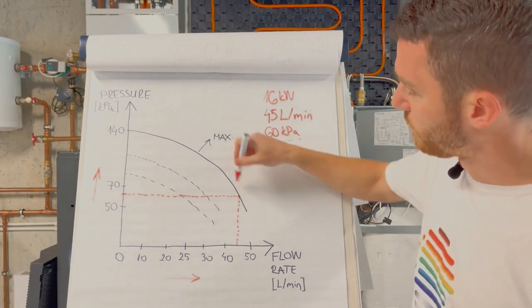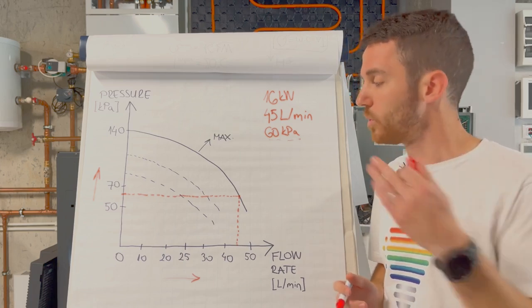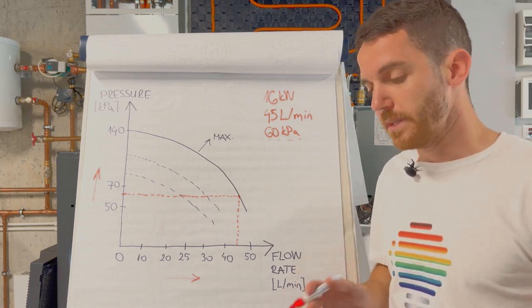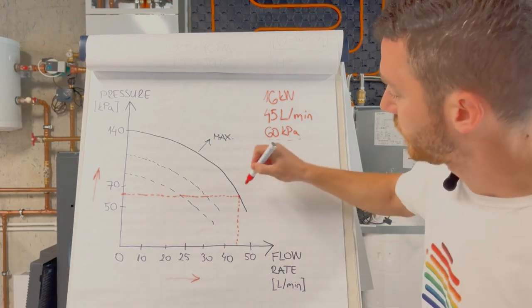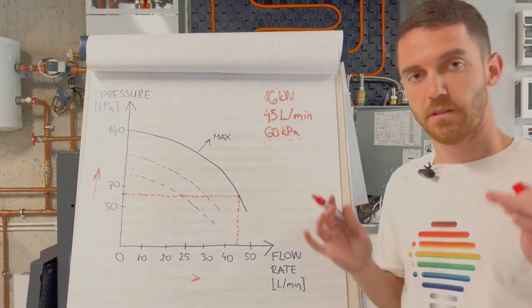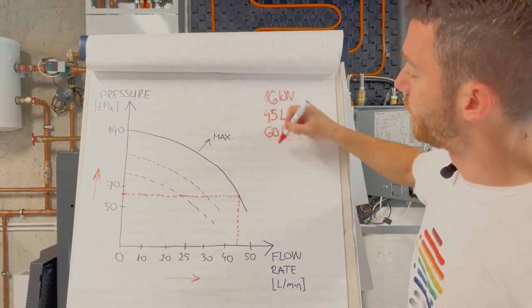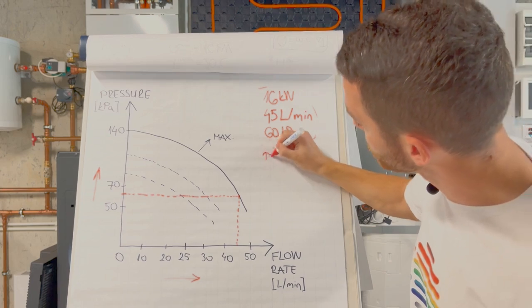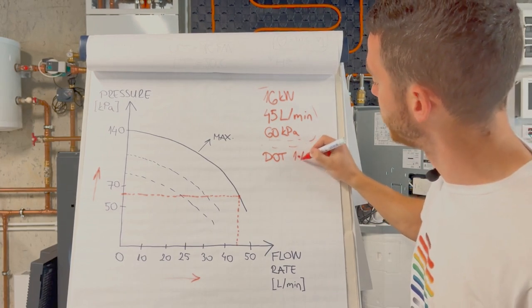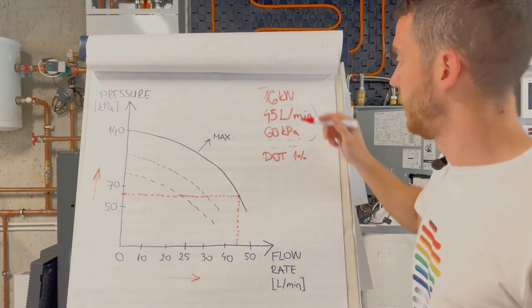What this also means, we have also some opinions that for maximum pump speed you will spend more energy running that pump than if you have two pumps, for example with buffer beside them. But this is not true. Here of course on maximum speed you will have really high consumption of pump. But as we showed in previous video, this is only design point, so design outer temperature, which means less than one percent of the year. It also means because our pump is modulating, when we have...